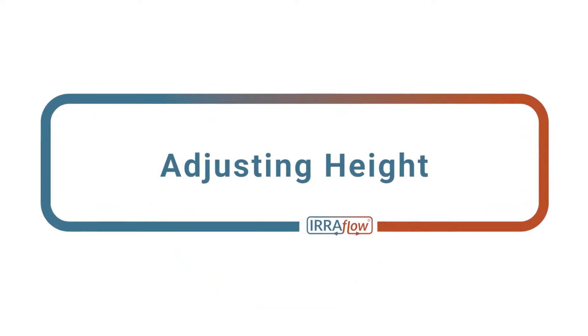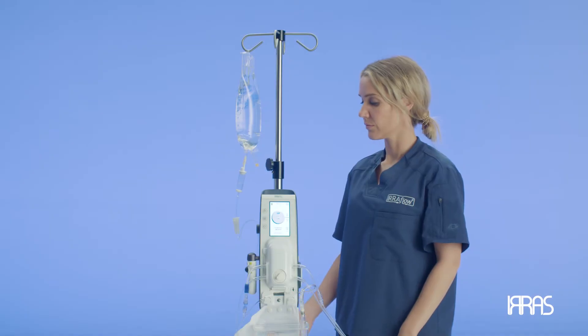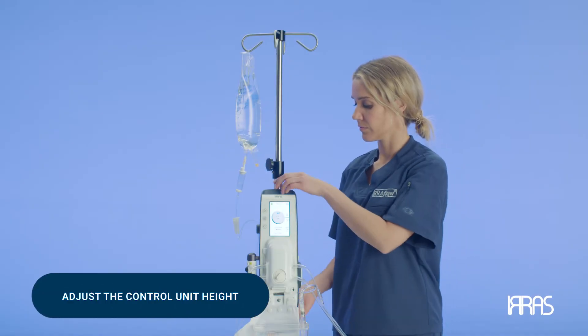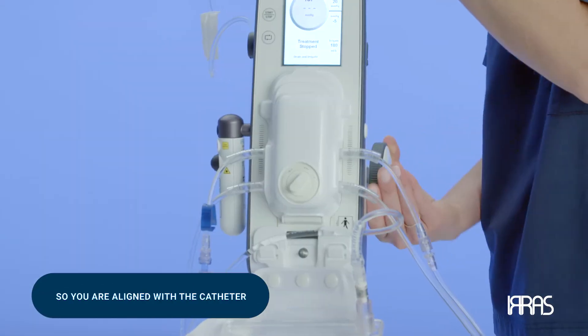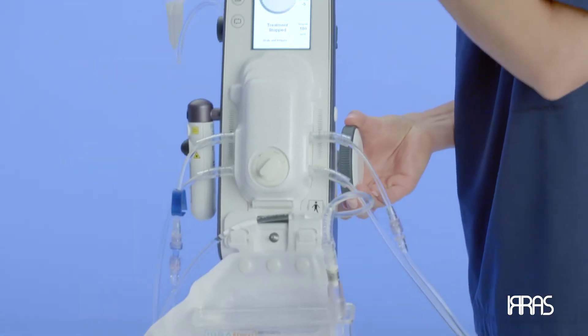Chapter 6: Adjusting Height. You have now successfully set the IRRAflow control unit up and are ready to adjust the control unit height so that you are aligned with the catheter. This will ensure you are obtaining the accurate ICP reading.